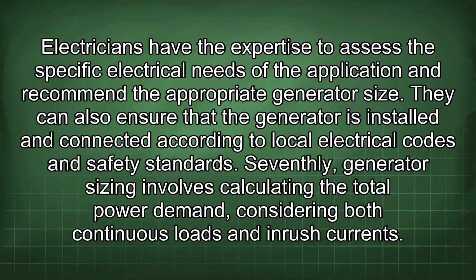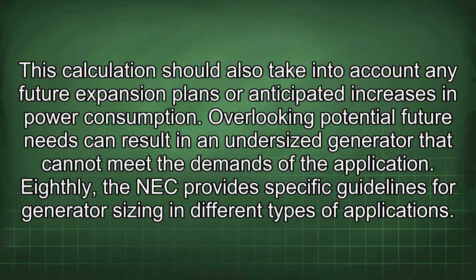Seventhly, generator sizing involves calculating the total power demand, considering both continuous loads and inrush currents. This calculation should also take into account any future expansion plans or anticipated increases in power consumption. Overlooking potential future needs can result in an undersized generator that cannot meet the demands of the application.